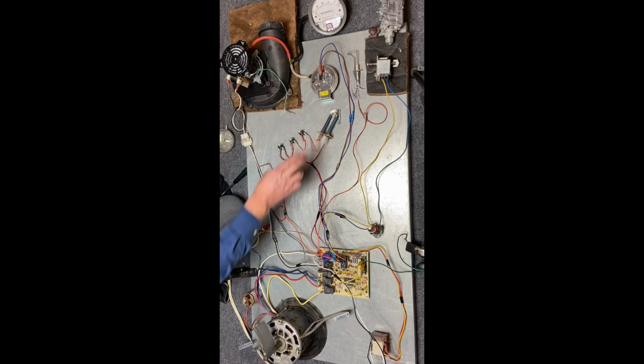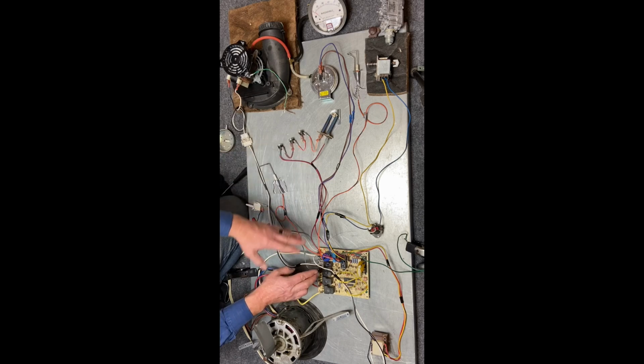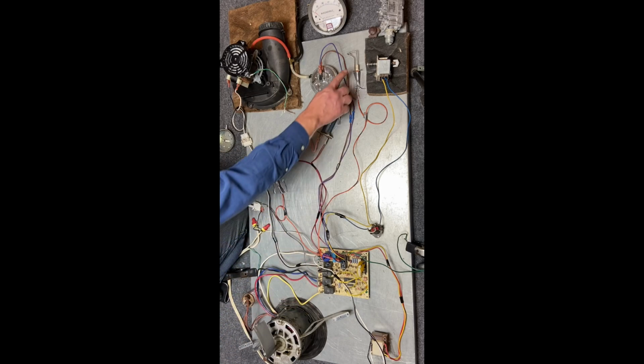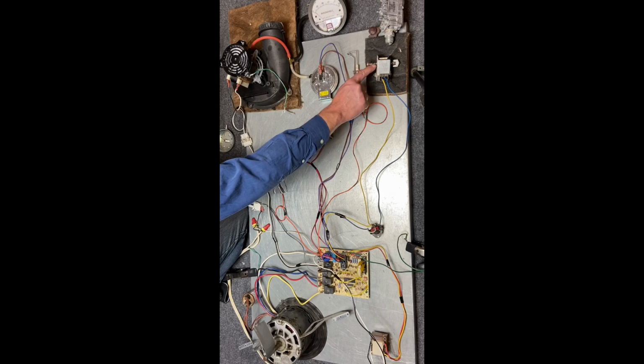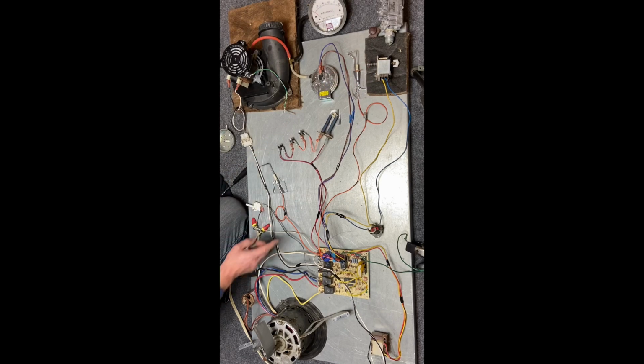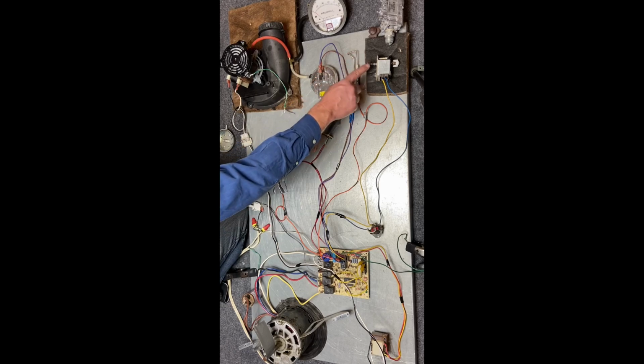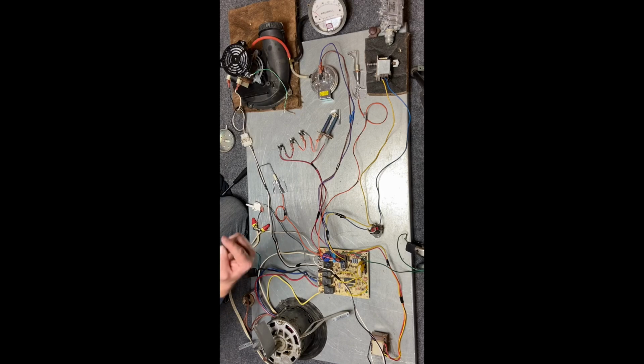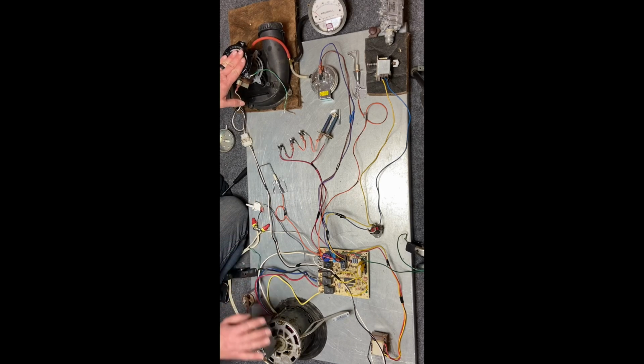This switch is going to close to the control board. These switches are already closed. Then it's going to energize our spark igniter and also energize this electromagnet, the solenoid, at the same time. Since we don't have a flame, then we'll stop igniting and it's going to release the electromagnet and this is going to pop right back out. And it will do that one more time before it goes into a safety, and it's going to keep this motor running and turn this fan on. But let's see exactly what happens.